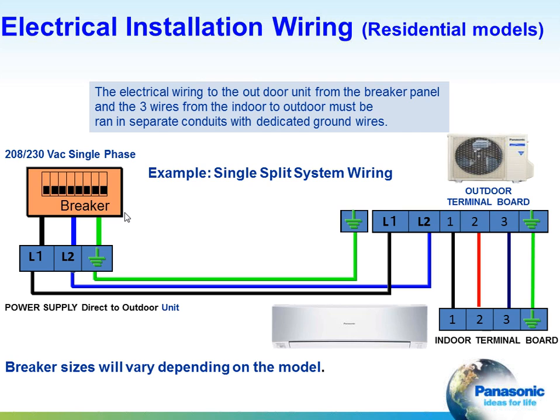In the wiring between the outdoor unit and the indoor unit, we want you to use 16 gauge stranded wire, and again, that gives you better continuity. The reason that continuity is so important is that this wire not only carries the primary power, but it also carries control signal as well. And control signals are very sensitive to discontinuities in wire, and sometimes the wire isn't quite what we desire, and so stranded wire covers both bases there.